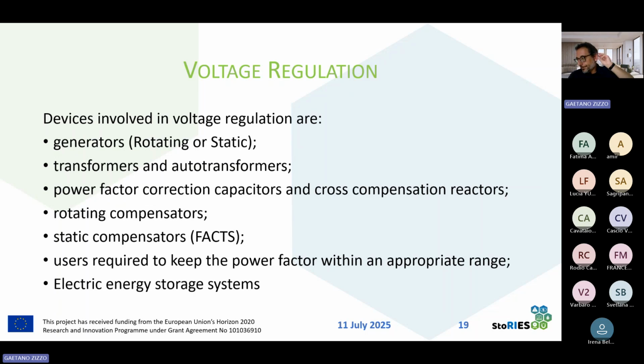Well, regarding this last aspect, when we vary reactive power, we usually do it for voltage regulation, but active power is usually managed in a given node for frequency regulation. Anyway, in many cases, in distribution grids, the variation of active power is necessary for having a better regulation of the voltage in a node more than the variation of the reactive power. So we can use battery also for this service.